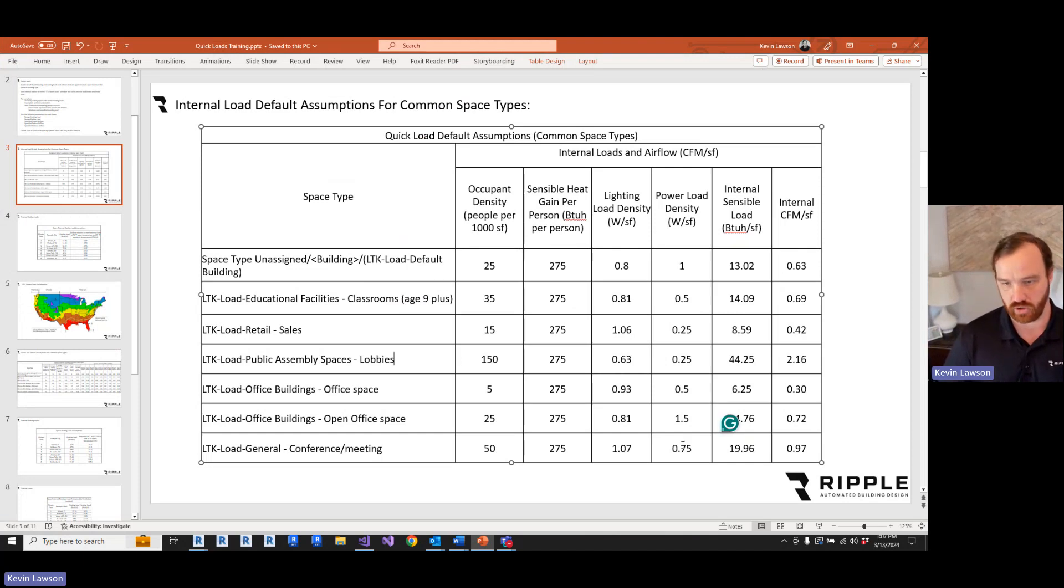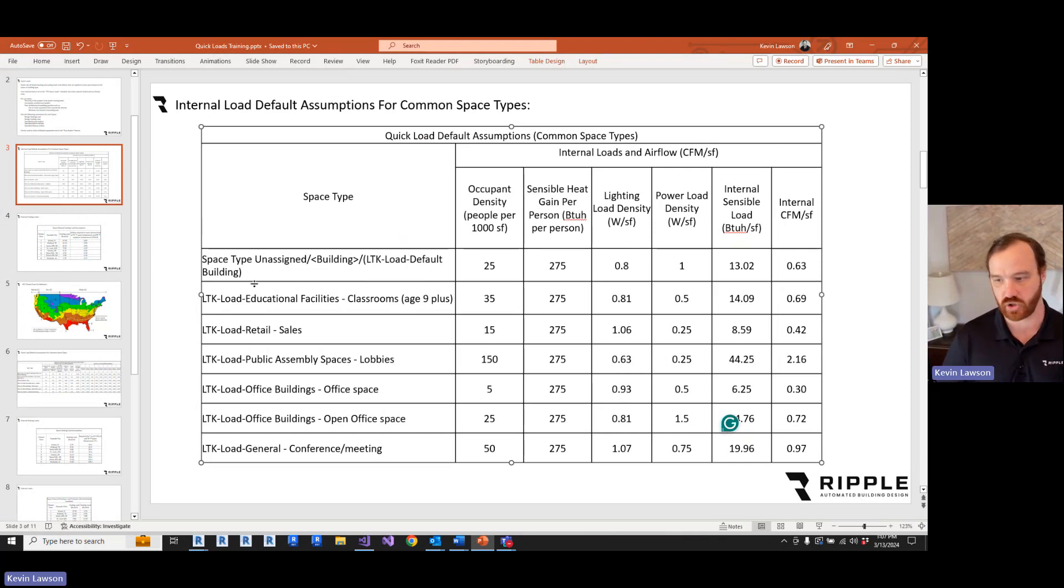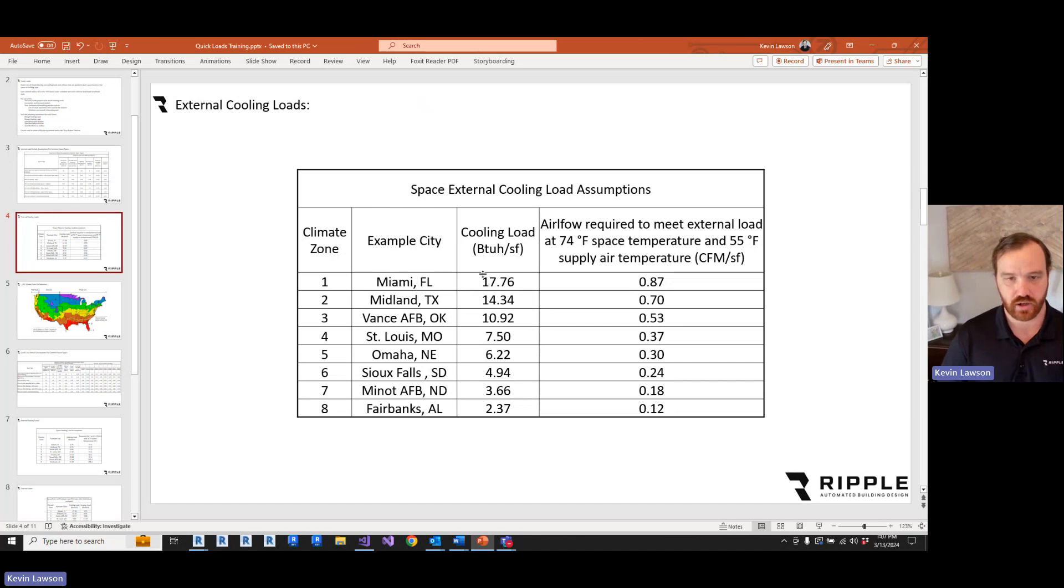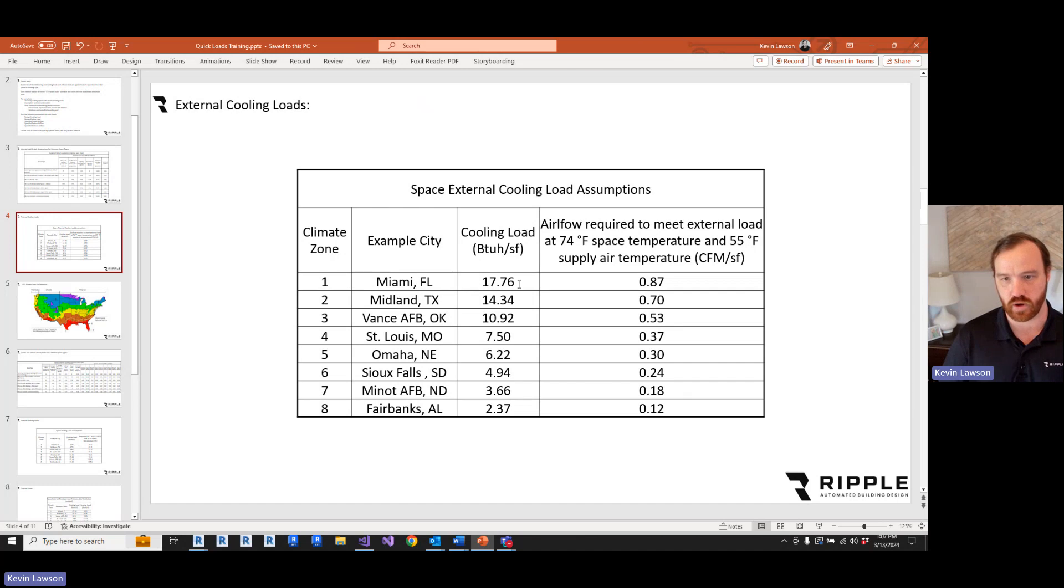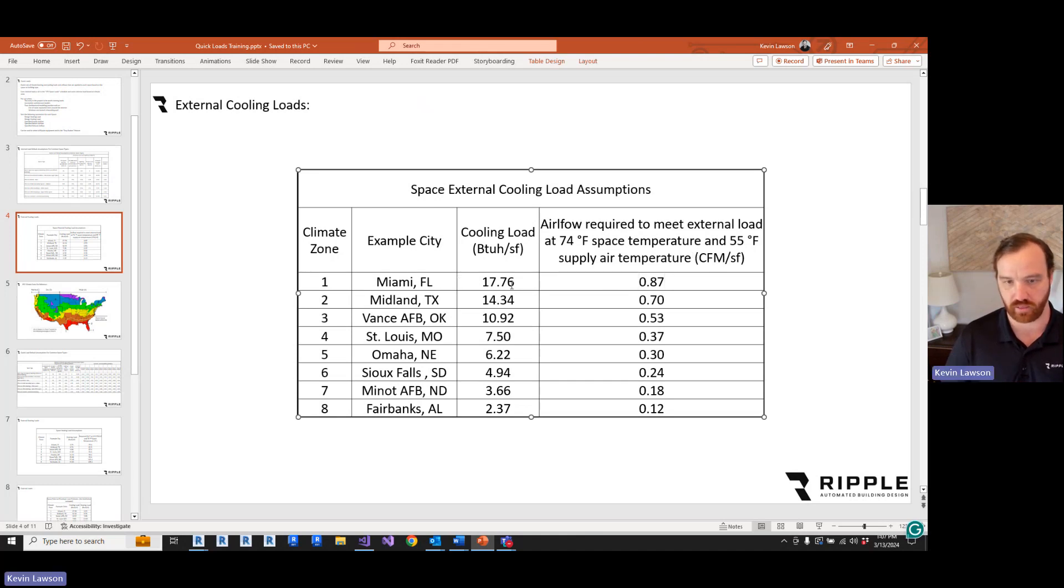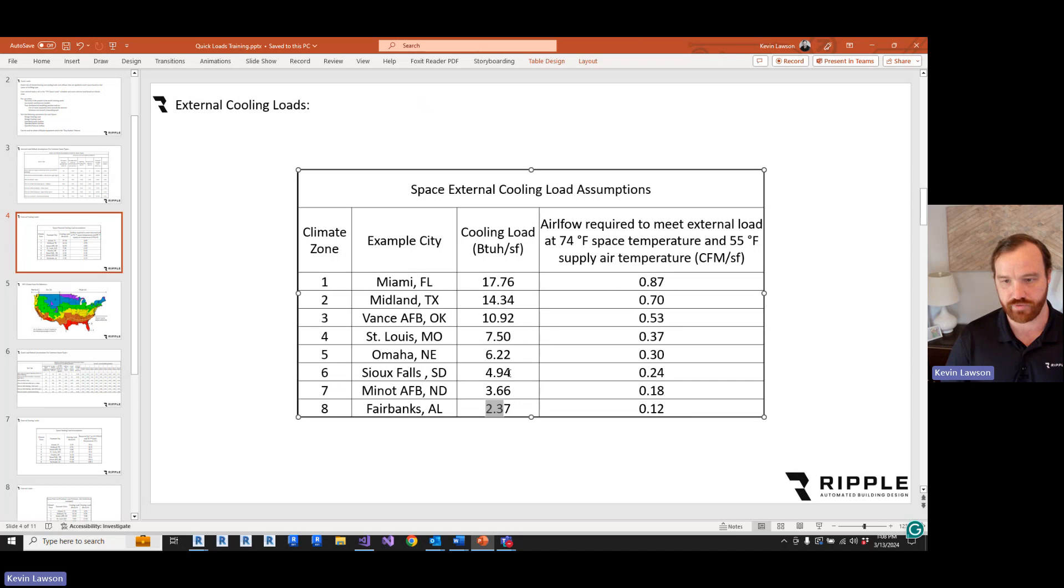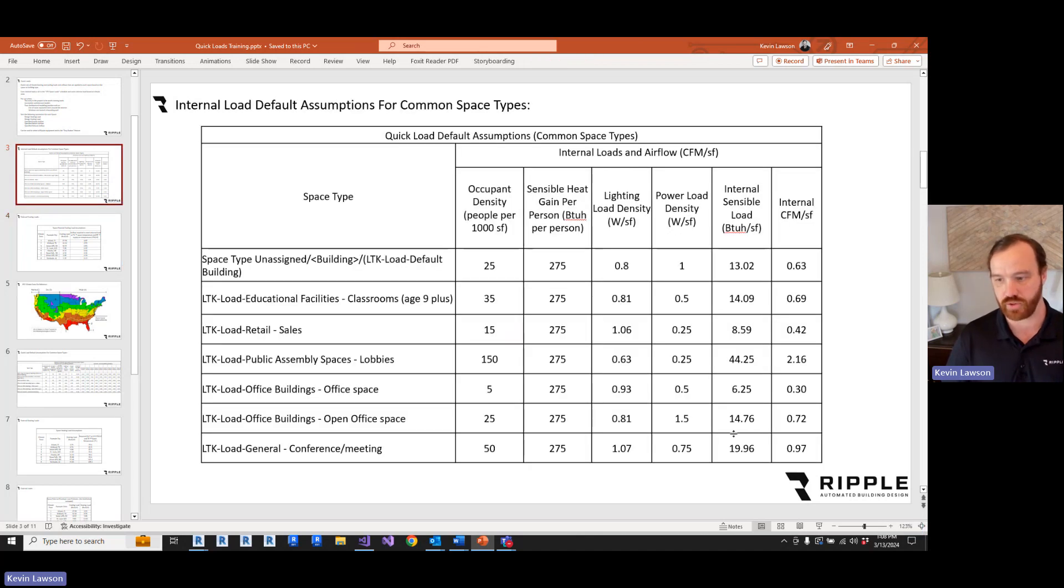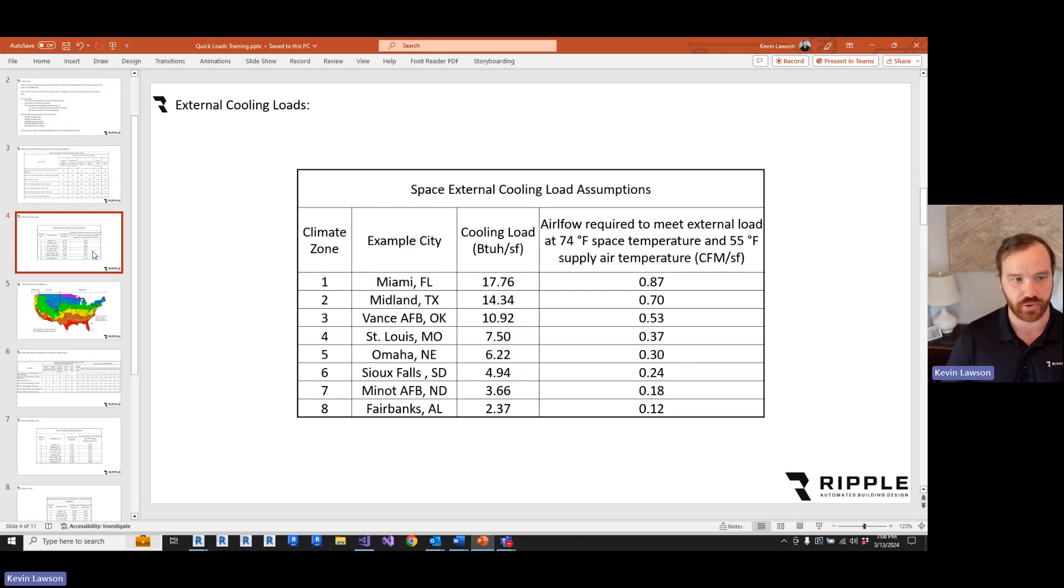So these are the internal loads, and these are going to be different for every space type. But what do we do about the external envelope loads? Here are the rules of thumb that I'm applying to every space. If you're in climate zone one, you're applying about 18 BTU hours per square foot. And just for the external load, it takes about 0.9 CFM per square foot to cover that load. And it goes all the way down to 2.37 in Fairbanks, Alaska. So this is going to be added to the internal load to come up with your total rule of thumb load.